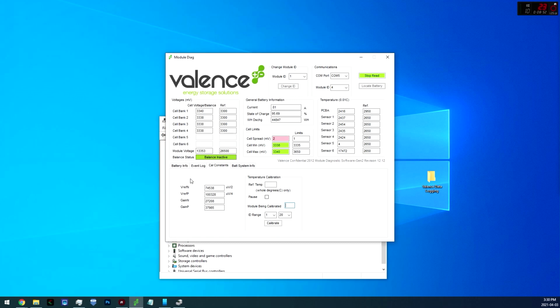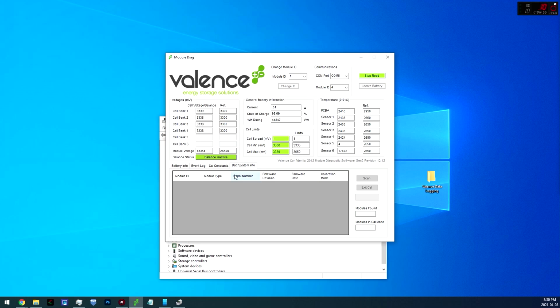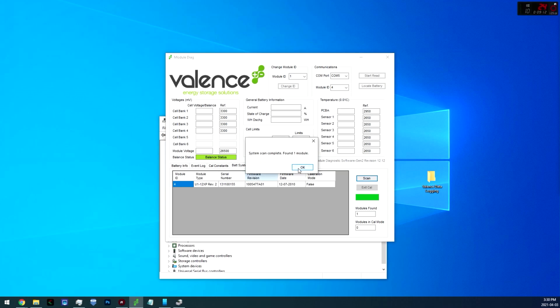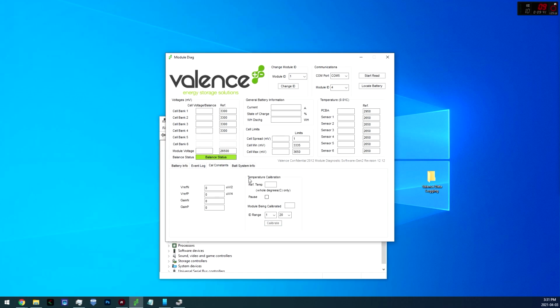So onto these other tabs that we have down here, we have bat system info. So if you go to stop read, once again, if you know your COM port now, you can go down and hit scan. So if you have a bank of batteries, this is gonna show you all the batteries in your bank with the module ID. So you can find the battery that you want in your bank, find the ID, type it in, and read individual batteries. You can also exit calibration. Boom. Make sure none of them are in calibration mode, and this is gonna exit all of them out of calibration mode. None of them are in calibration mode anyways, but if you had them in this calibration mode right here.